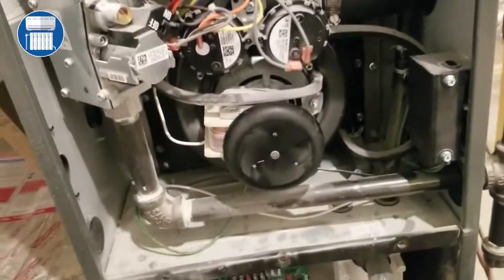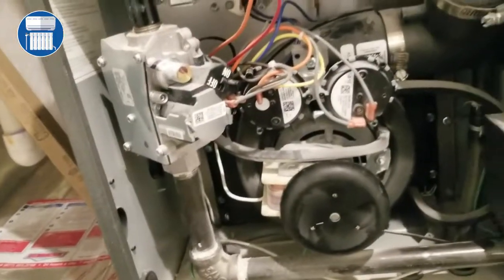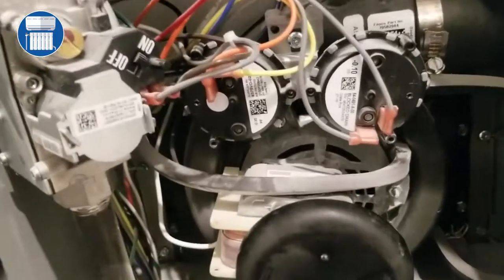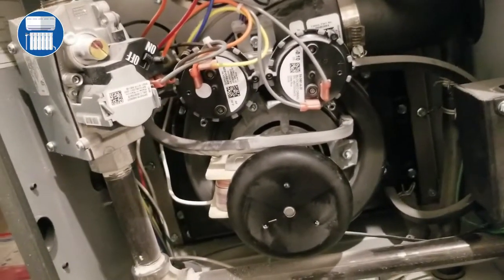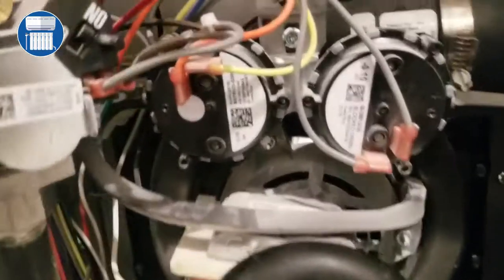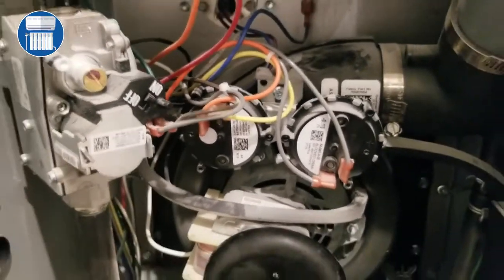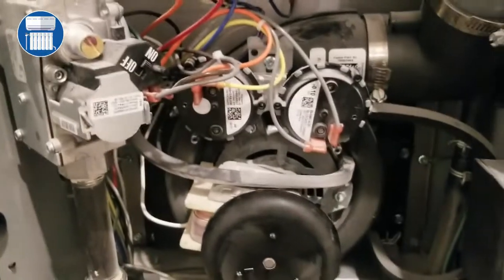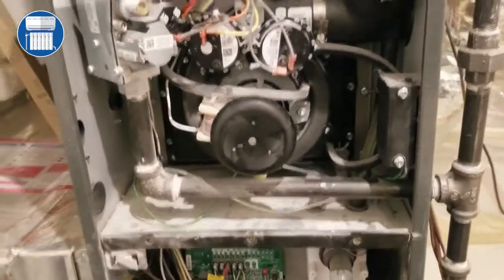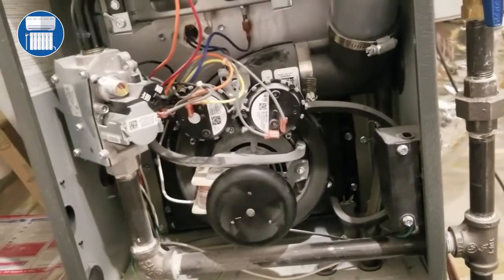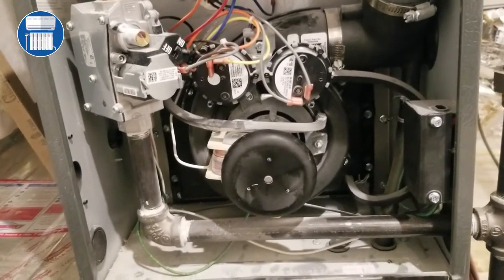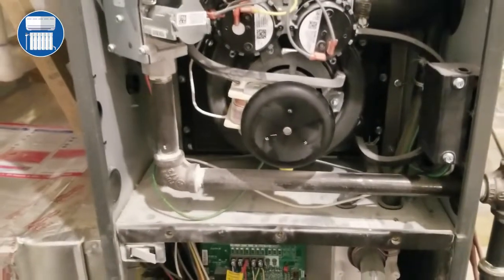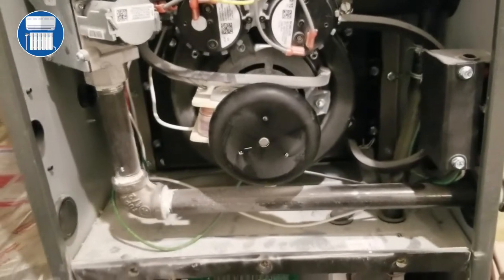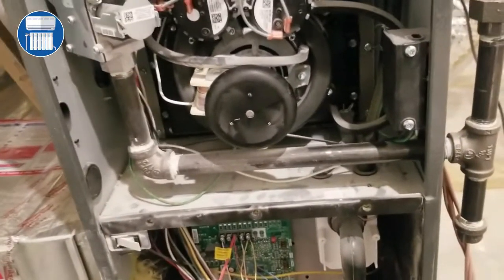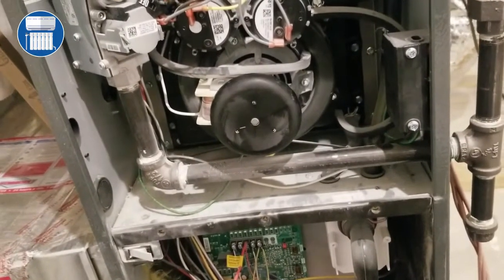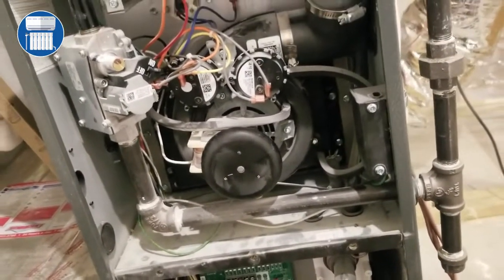So the pressure switch is one of the major problems that we can run into. Another issue is open high limit. Let me talk about the open high limit. It would be one of your limit switches. It will tell you open high limit, and it means that the air or the heat from the furnace cannot escape. So there's a restriction. Most times that happens because your vents are closed, or sometimes we have dampers in the unit. These dampers are closed, so you may want to check your vents and open your vents, or if you have dampers, check downstairs and look through your duct and see if you have dampers.